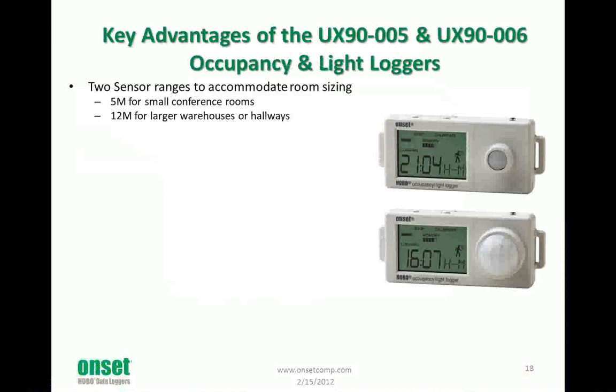First, taking a look at our new measurements here, the occupancy and light logger. It's available in 2 different ranges. The smaller one, the image on top with the smaller sensor, is rated for 5 meters, and the other for 12 meters. In smaller conference rooms you'll want to use the smaller sensor, made for picking up smaller movements—I'll show a graph on how that works. The 12 meter is for hallways or large warehouses where people are walking by, or you may have forklifts going by. The signal strength indicator ensures not only that the occupancy sensor is located where it's picking up the whole room, but also validates that you're getting enough lighting to the light sensor for good readings.